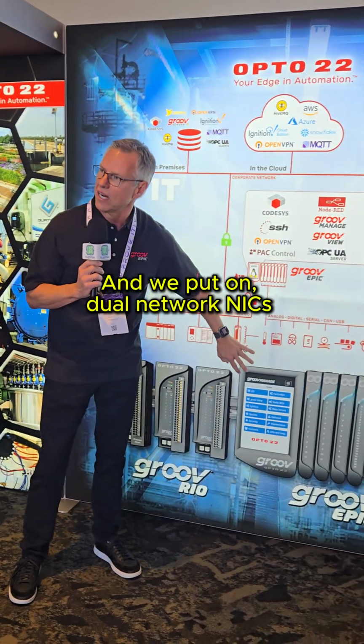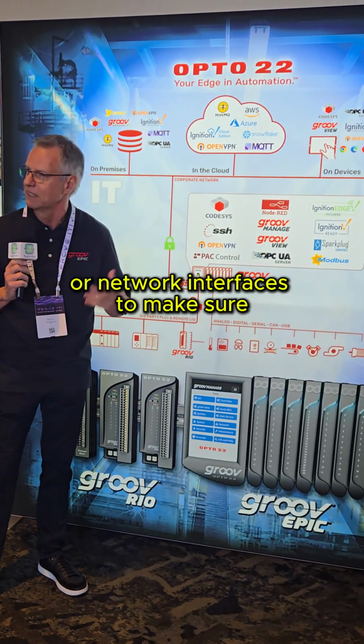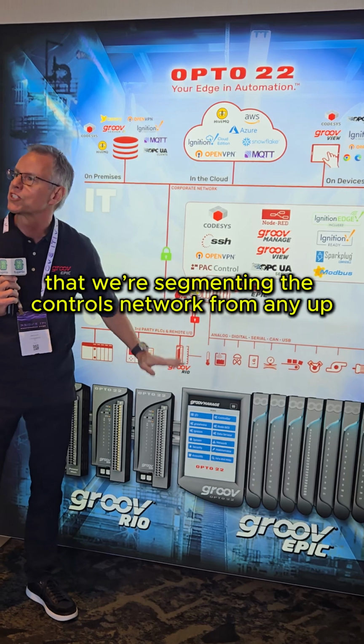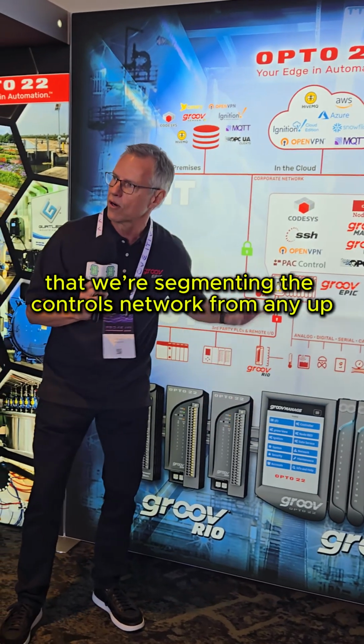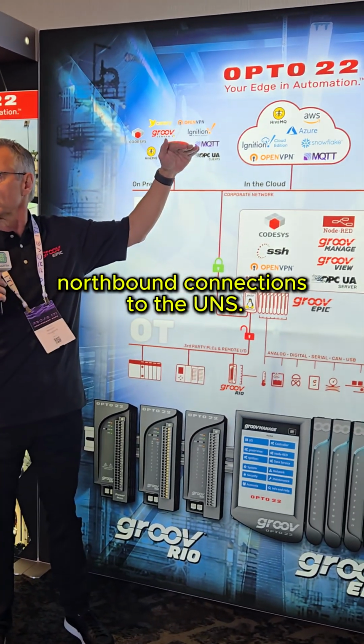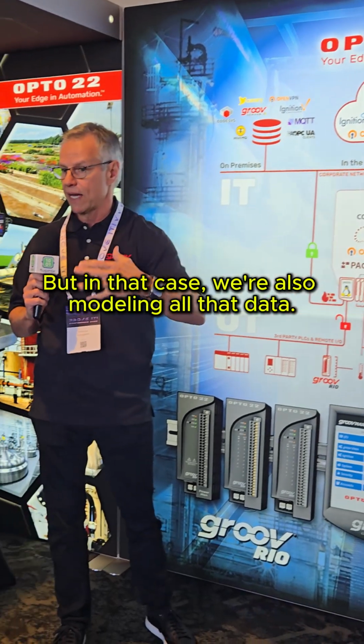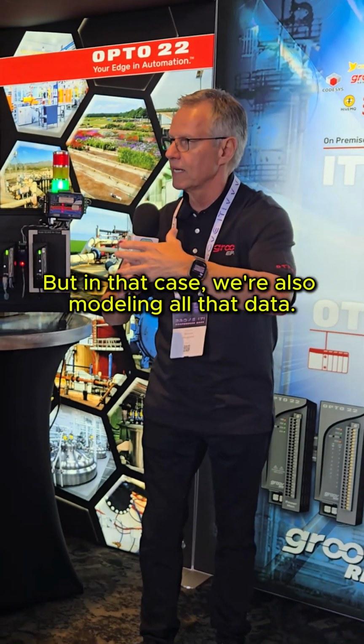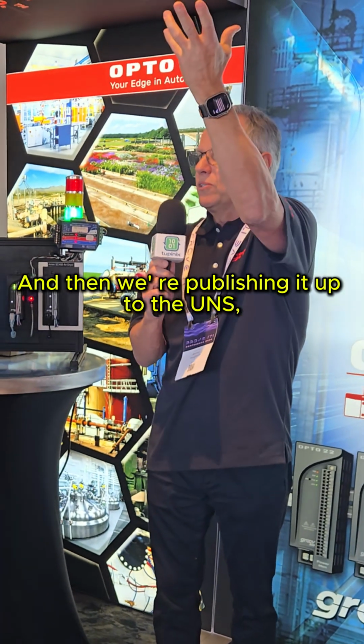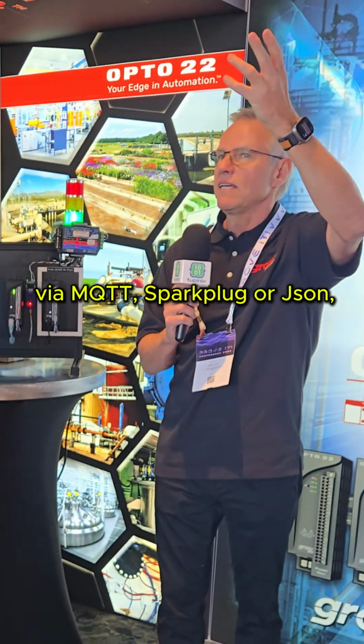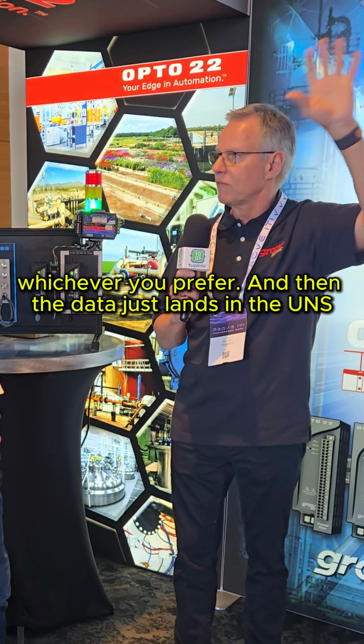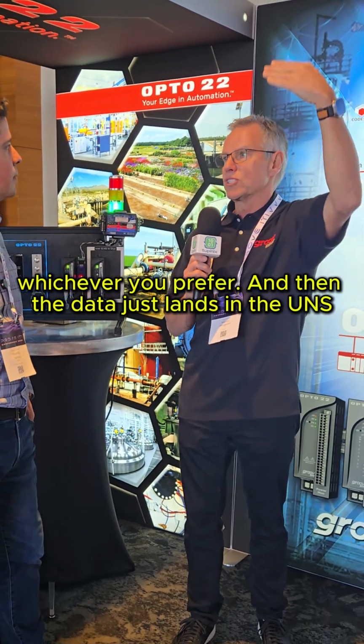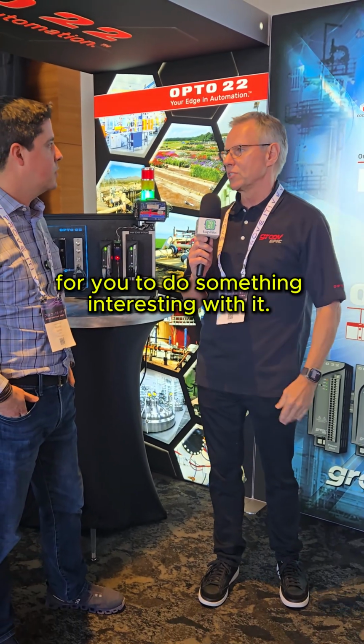So we can prevent unauthorized access to these devices from any network. And we put on dual network NICs, or network interfaces, to make sure that we're segmenting the controls network from any northbound connections to the UNS. But in that case, we're also modeling all that data, and then we're publishing it up to the UNS via MQTT, Sparkplug or JSON, whichever you prefer, and then the data just lands in the UNS for you to do something interesting with it.